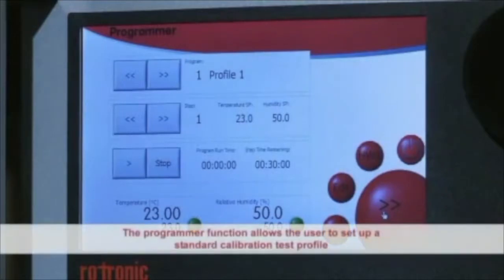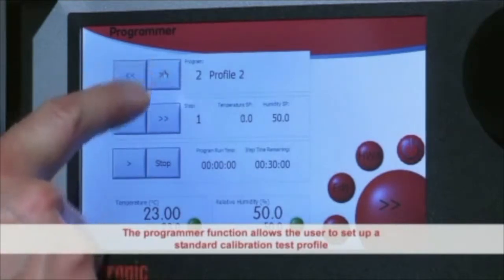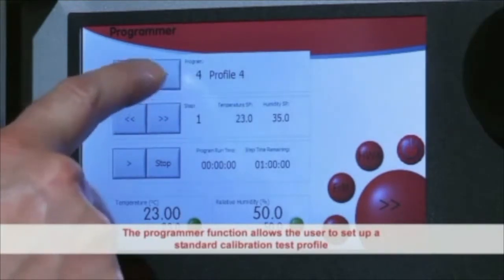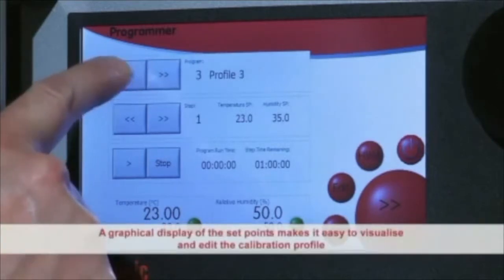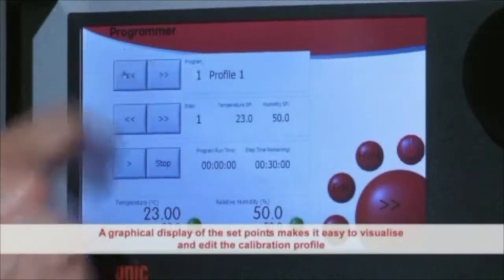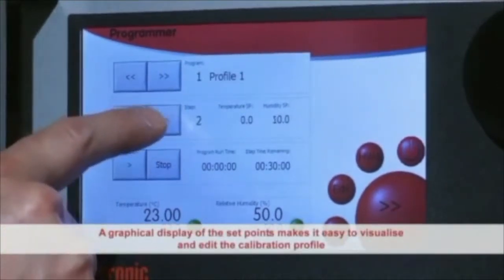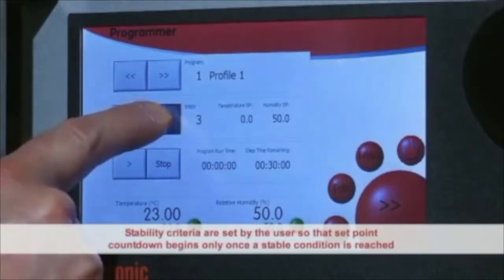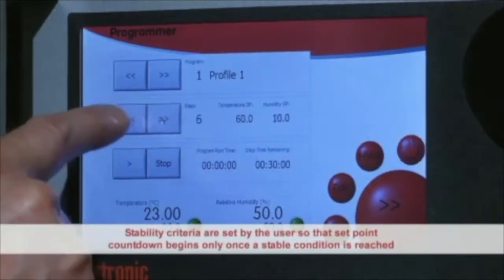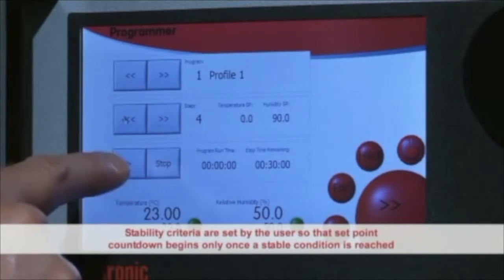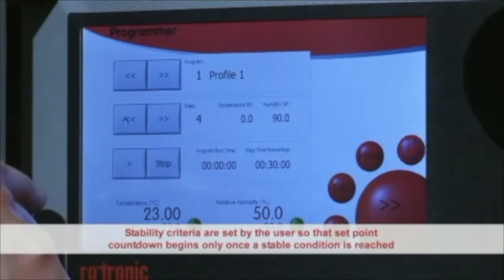The programmer function allows the user to set up a standard test profile. A series of temperature and humidity set points can then be run without user supervision. A graphical display of the set points makes it easy to visualize and edit the calibration profile. Stability criteria are set by the user so that set point countdown begins only once a stable condition is reached.